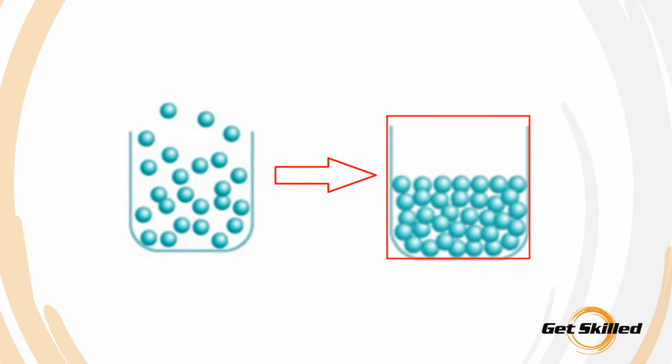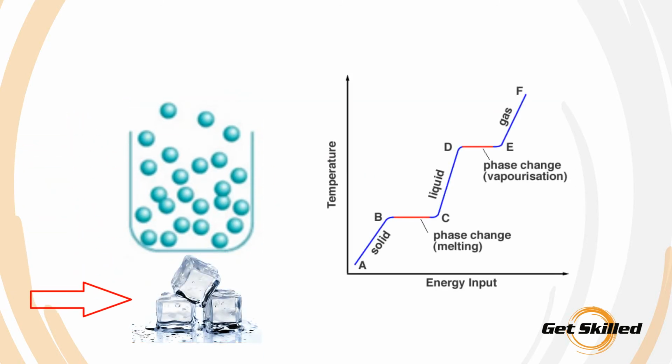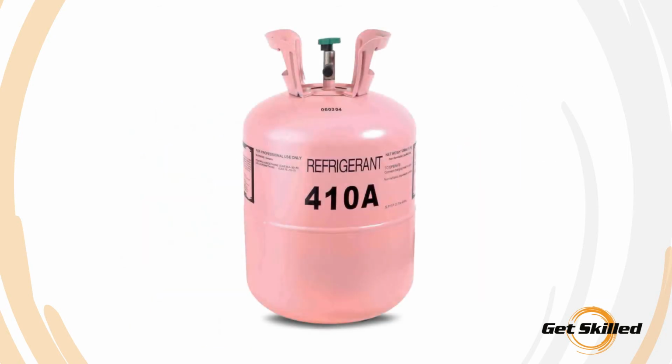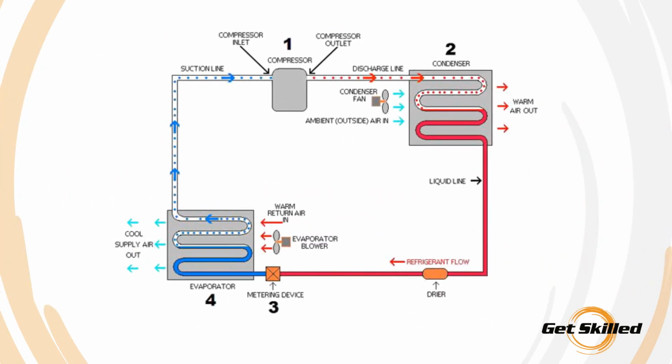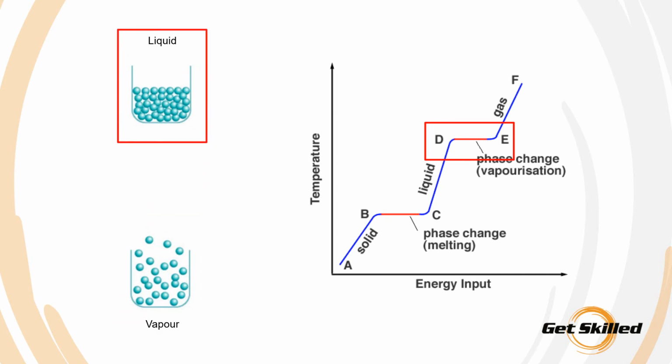Before a superheated vapor can be condensed back to a liquid, the vapor must be desuperheated. That is, the vapor must first be cooled to its saturation temperature. Heat removed from a superheated vapor will cause the temperature of the vapor to decrease until the saturation temperature is reached. Refrigerant is usually desuperheated within the system by the air flowing over the coils and removing heat. At this point, any further removal of heat will cause a portion of the vapor to condense to a liquid.